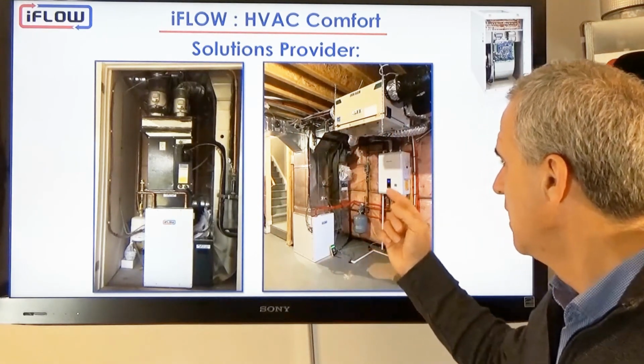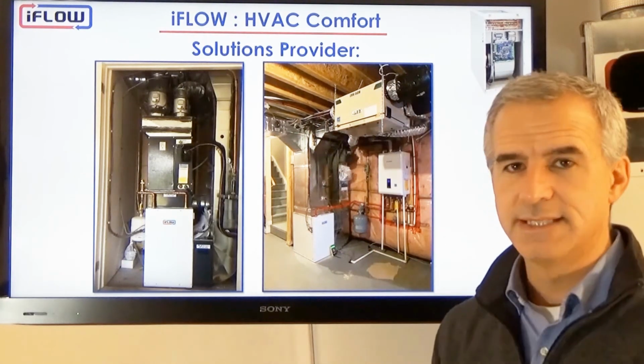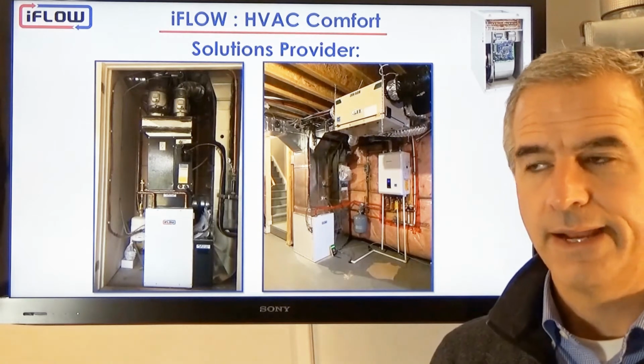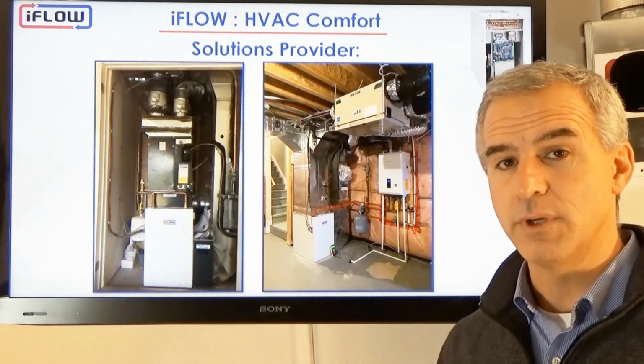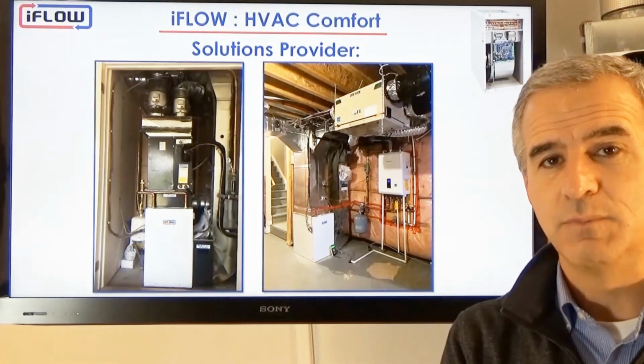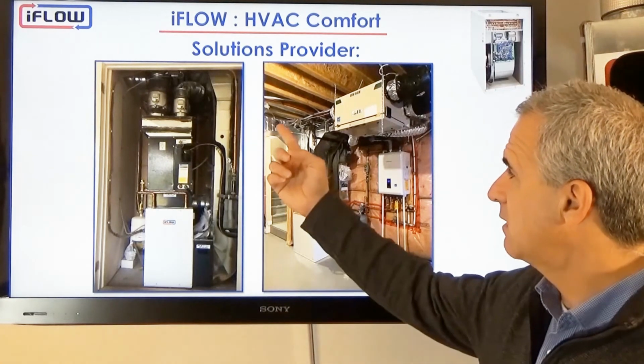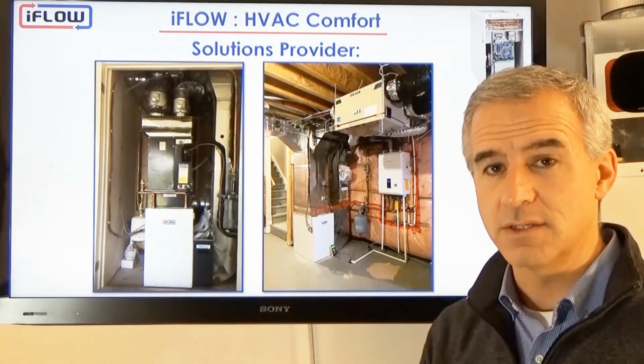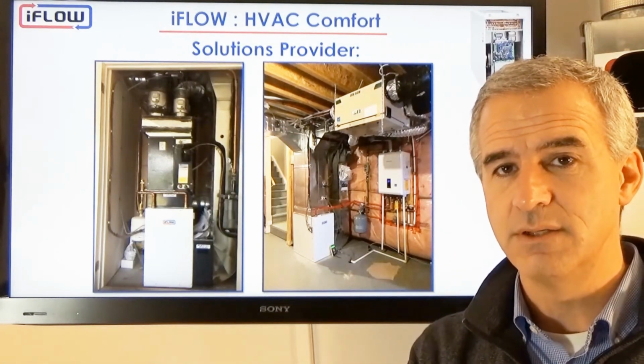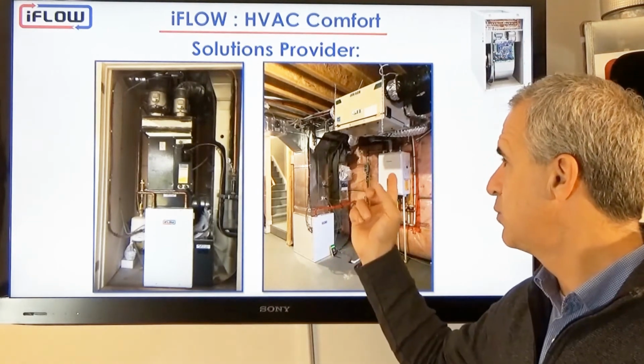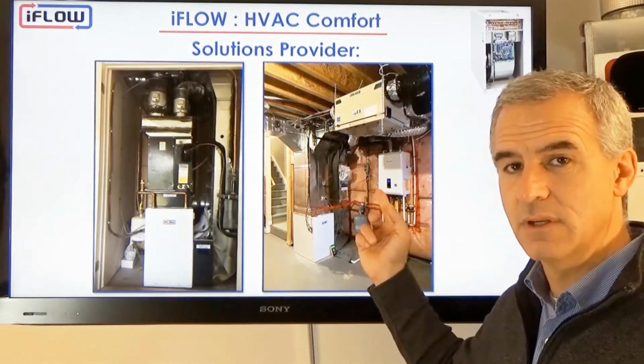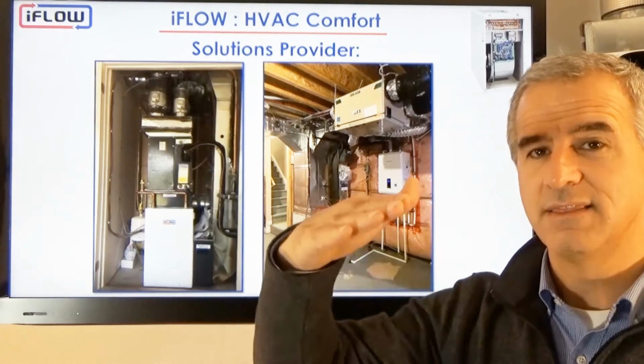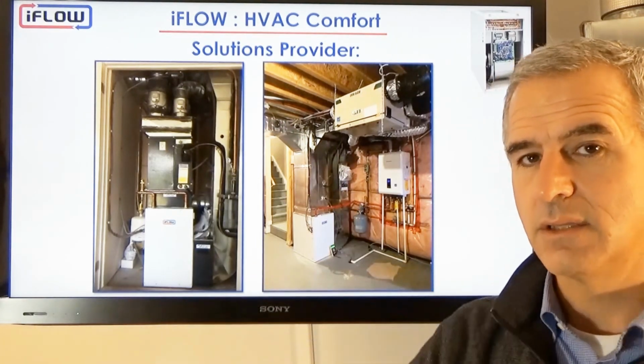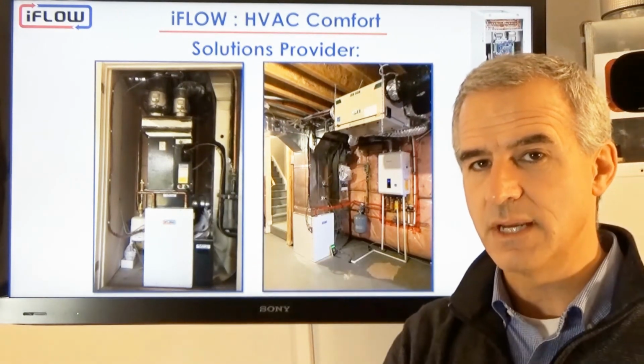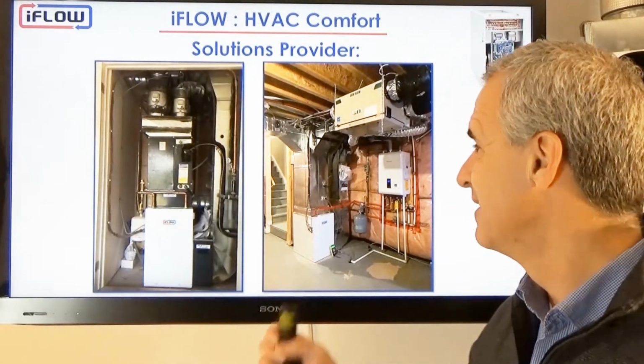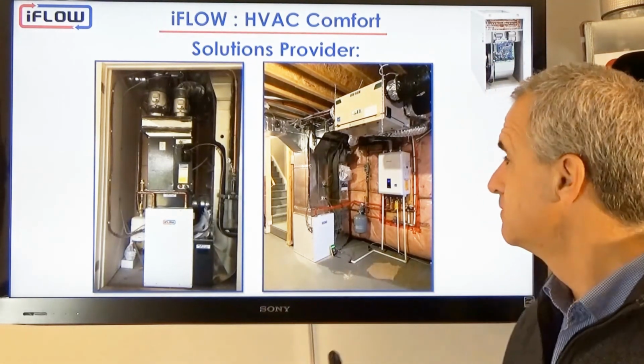So in this case, for example, if that was a 60,000 BTU boiler and it had a 10-to-1 turn down ratio, it could modulate down to 6,000 BTUs. So if my minimum heat loss on one zone was 10,000 BTUs, this unit could easily provide that, because its minimum is 6,000, it could easily ramp up to the 10,000 and deliver all of the heating we need without cycling, with great efficiency. That's a great solution.